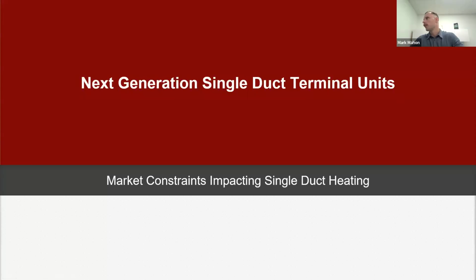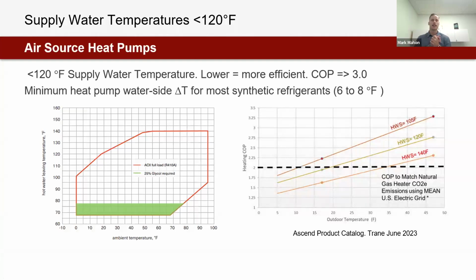Absolutely. Just to give us a bit of a backdrop to address that, because I think it's an excellent question, I'll jump ahead. We'll see this slide later. But I think broadly, when we look at climate zones 5 and 6, the challenge is the air source and the ground source heat pump is not really built for the environment we're existing in. That's because, looking here at the Ascend from Trane, a very popular air source heat pump, when we look at the ambient temperature, our hot water supply temperature quickly decreases for this air source heat pump as our ambient temperature decreases. We're essentially at the wrong end of the relationship between ambient temperature and hot water leaving temperature, because of course Wisconsin on design day in the winter is cold, so that means we need more heat, but it also means we get less temperature.